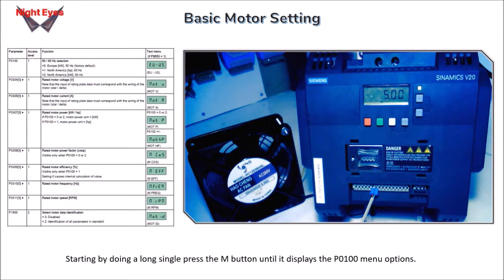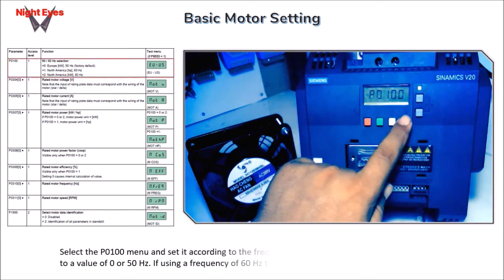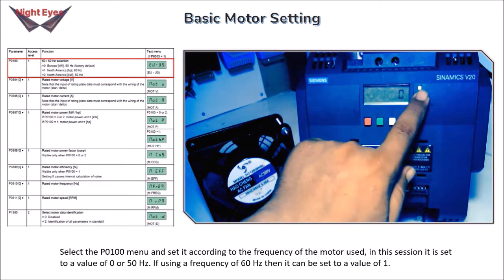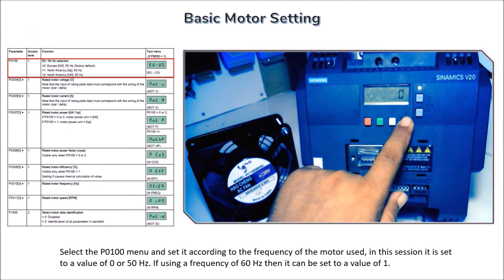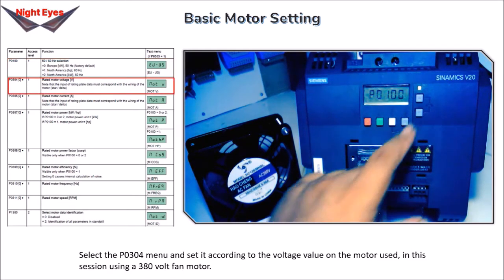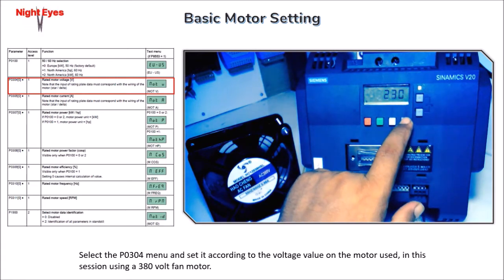Start by doing a long single press of the M button until it displays the P0100 menu. Select P0100 and set it according to the motor frequency — in this session it is set to 0 for 50Hz. If using 60Hz, set it to 1. Then select P0304 and set it according to the motor voltage — in this session using a 380V fan motor.